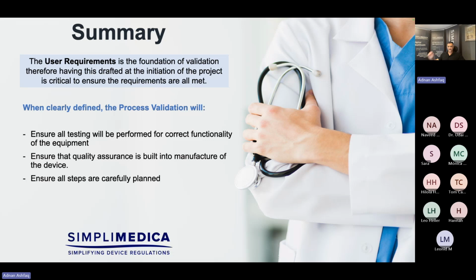So once we've got the user requirement or the design requirement in place, that will allow us to have clearly defined the process validation, will then allow us to ensure equipment testing is done correctly for the functionality, ensuring that the quality assurance is built into manufacturing the device, ensuring all steps are carefully planned, ensuring all stages are documented, and ensuring also all stages are in the correct order as well. So those are all the important terms to consider once we're having a look at process validation. That completes my presentation for today.